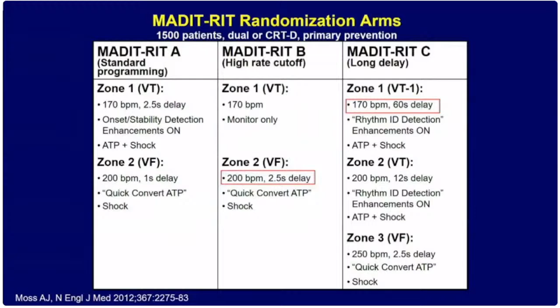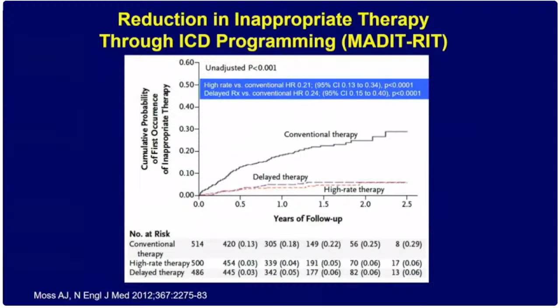In the second VT zone, the delay was 12 seconds at 200 beats a minute detection. And for 250 beats per minute, it was a 2.5 second delay. So that was called the long delay zone. And then the other one was the high rate zone. Those are the 2 non-standard zones. And then the study showed pretty clearly significant difference. You could see conventional therapy, time to inappropriate shock therapy, much better with either delayed therapy or high rate therapy compared to conventional therapy, statistically significant.